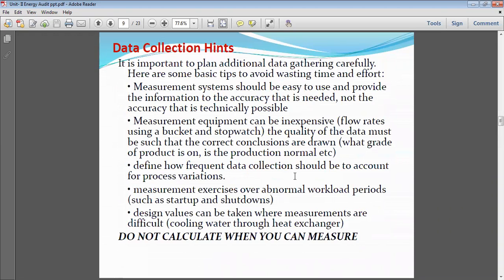We have come to a very important point: during the detail energy audit, we have to collect data related to the machine, and that data collection should be such that we should not calculate from standard formulas. We have to collect as much as possible whatever reading is taken from the measuring instrument. So the point is, do not calculate when you can measure.